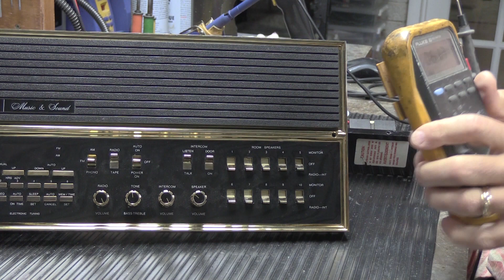If the transformer is being overloaded, meaning the device is demanding much more power from the transformer than it reasonably can supply, the voltage output of the transformer would drop noticeably, could drop as much as down to 1 or 2 volts because it's seriously overloaded. Also, in those situations, the transformer tends to get hot pretty fast. This one, not so much. So I don't think that's the problem.